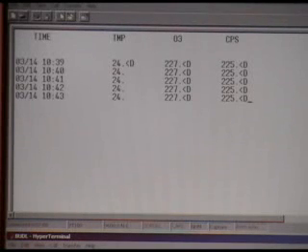As I said before, we were going to check our temperature probe today for the site temperature to make sure it was reading correctly. And it was reading a little bit high as compared to our NIST standards, so we had to go back in and change it. I'm going to show you what we did to change it.